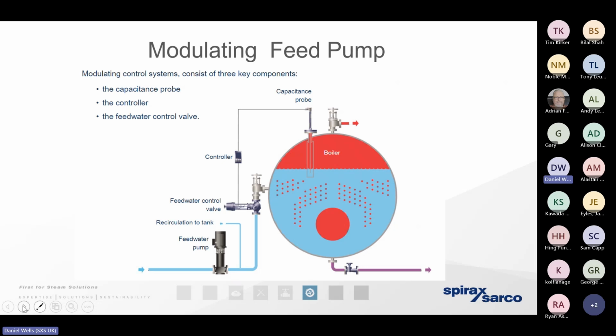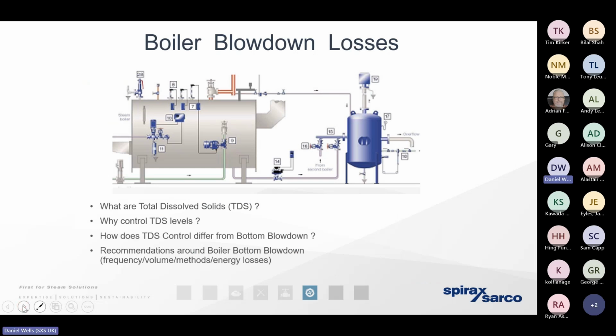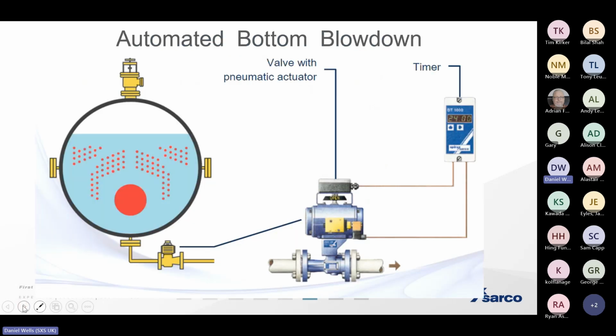And that would have a greater demand of energy and also a burden of maintenance. The blowdown, we've looked at the blowdown in some detail in previous presentations. Blowdown is the means of maintaining the correct water chemistry within the boiler. So we want to perform what we call bottom blowdown to ensure that that heavy particulate is adequately flushed away.